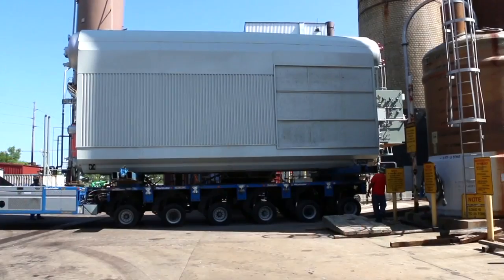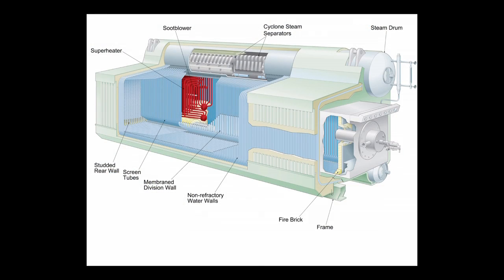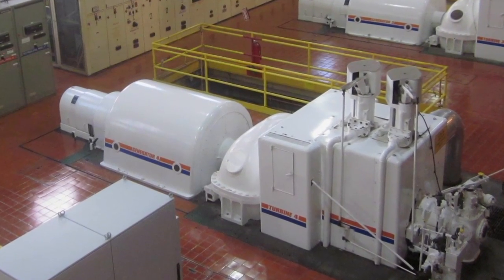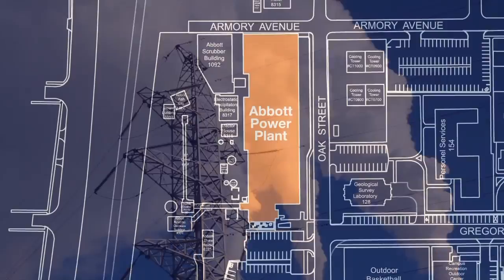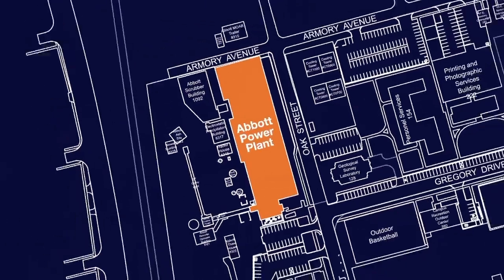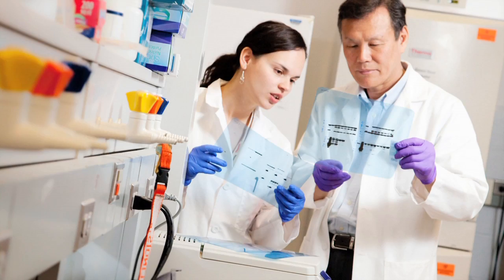The second system consists of water tube boilers powered by natural gas, which can also run on fuel oil if the gas supply is interrupted. The boilers convert water into high-pressure steam, which is fed into a turbine that spins a generator to produce electricity. In a conventional electric plant, all that heat in the steam would be wasted. Here, it's captured and distributed to the campus through a vast network of underground pipes to heat dorms, classrooms, labs, and other buildings.